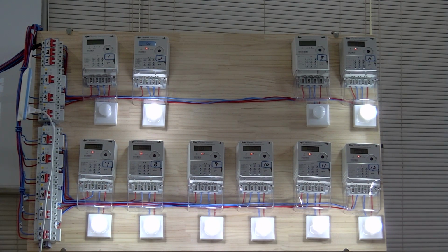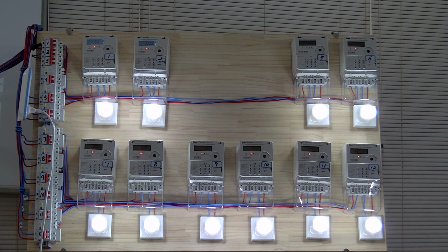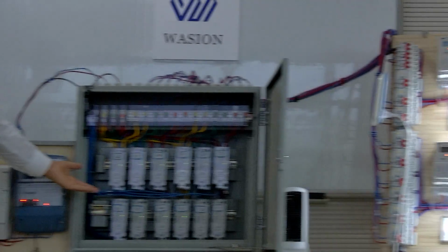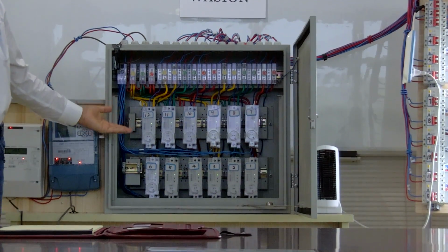The system does not connect meters at the same time, but connects them one by one to prevent shock to the electrical grid. So the consumption will rise smoothly, not very sharply, which is not good for the transformer and for the utility grid. And number 5 will be connected shortly. Okay, it's connected. If you check the check meters, you will see that all of them are connected.